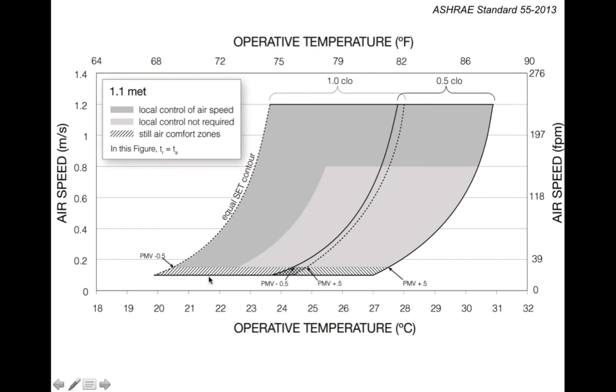So in fact, less than 0.2 meters per second. The light shaded portion that you see here, let's look at more of the summer comfort zone. You don't need local control of airspeed. This could be a ceiling fan or a table fan kept in the middle of the room and serving a few occupants. It could still achieve even up to 0.8 meters per second. You are able to see a level of comfort.